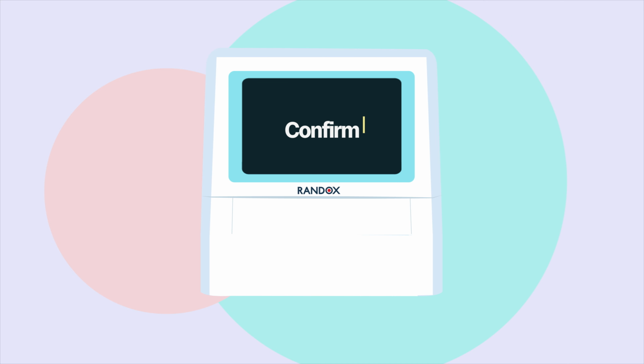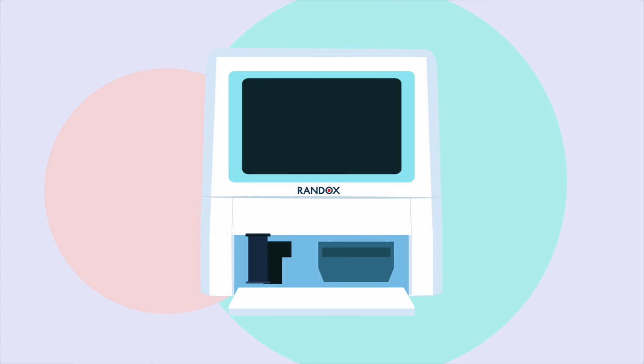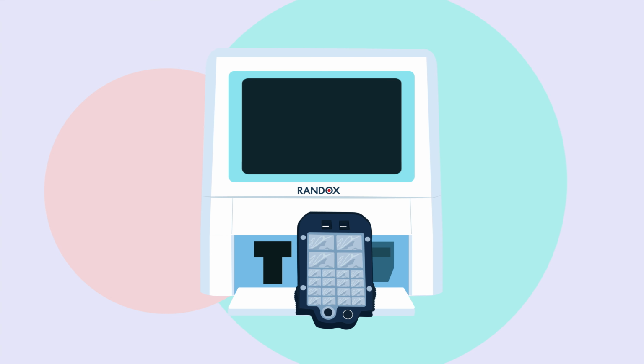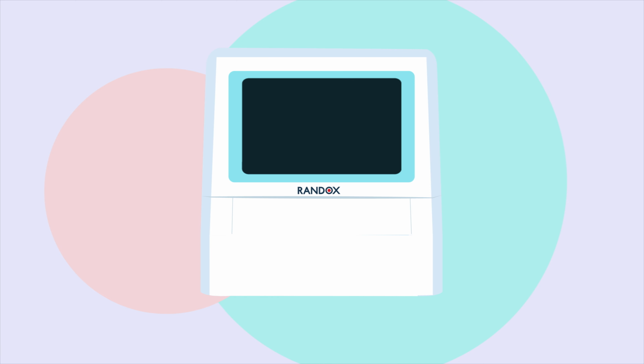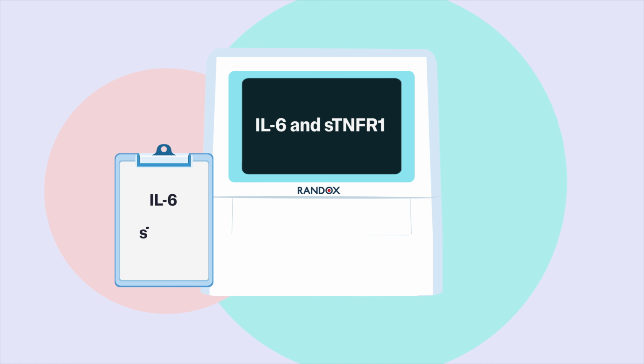Press Confirm. Wait for device to perform checks and select Run Test. Once run is complete, select Eject Drawers and remove the used cartridges to discard into biohazardous waste. Push empty drawers back into place, close the door and select Confirm. Concentration values for IL-6 and STNFR1 will be shown on the screen. Make a note of these values and the time to enter into the ECRF to randomize the patient.